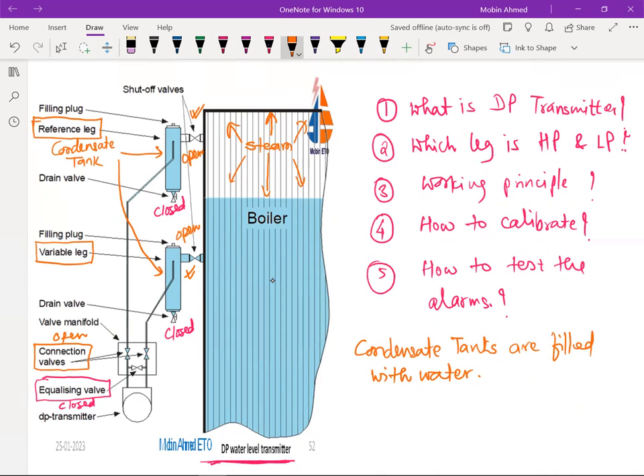No. Okay. The candidate who has given the answer that the reference leg is a high pressure leg is absolutely right, but the justification is wrong. How he justified it is wrong. This is not due to the steam pressure, because it is a closed vessel. Vessel means drum, container. It is a closed container, and in a closed container the pressure is equally divided, meaning it is equally applied on the sides. It is a steam pressure here, the pressure of steam, so it will be applied on all sides equally, not only this side, but in the water also the steam pressure will be applied. Yes or no?